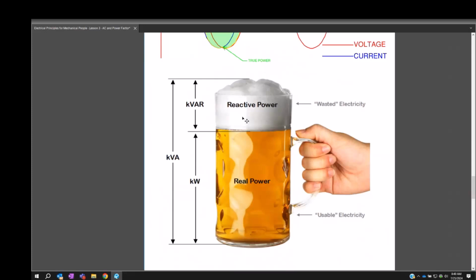So whenever you see kVA, that's not the actual amount of power that you can get from that motor, because it's including the reactive power, which is the needed power to get it going or get it started. Correct, that is correct.